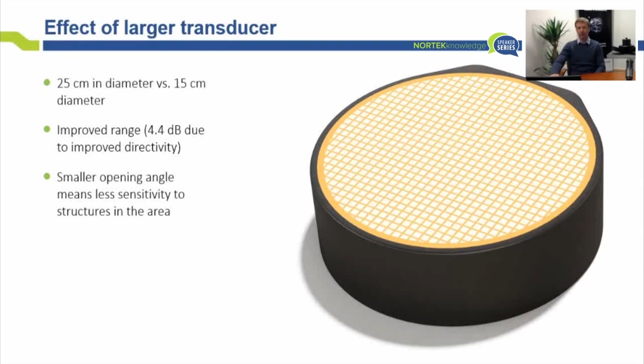So that means that when you mount something like this on a structure where you may have interference from things that are mounted in the vicinity of the system, you have a little more suppression of the energy coming back. That is true at least when it's operating at 75 kilohertz. When you operate the system at 55, and this really is a dual frequency system, the larger transducer is really partially just recapturing the size that, in a way, we lose because we're at the lower frequency. So the effective beam width obviously becomes larger again when you go down to 55. And they're actually about the same as the current 75s that are out there in the market. So there are some numbers that worked out that way. But from the get-go, the improved SNR and the smaller opening angles were the two main factors and reasons for making these into large transducers.